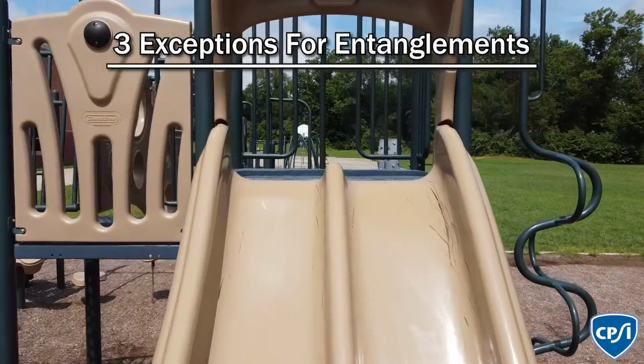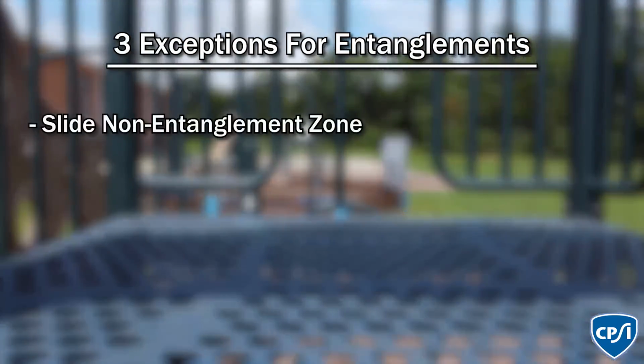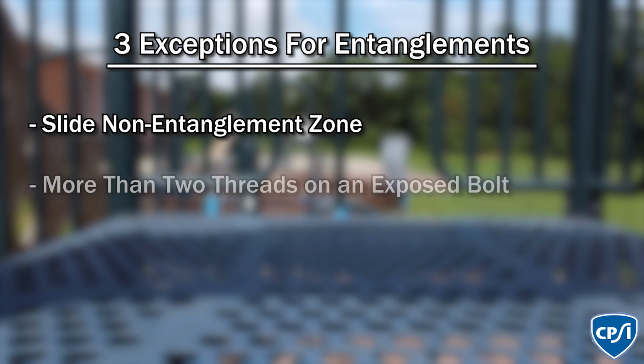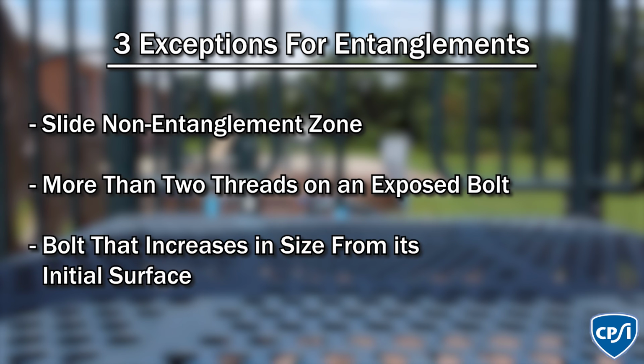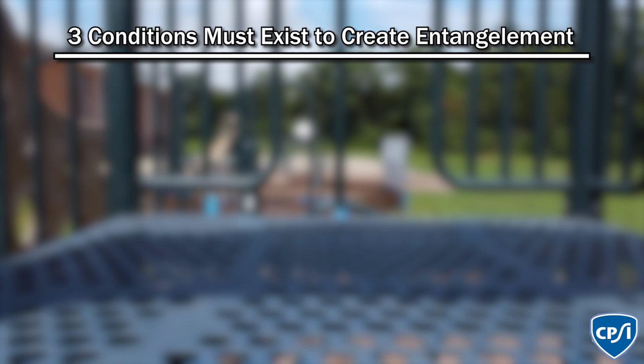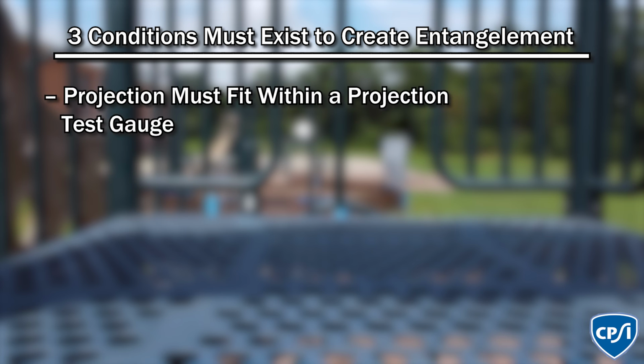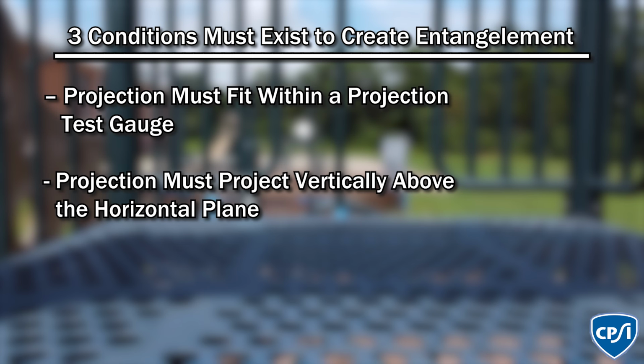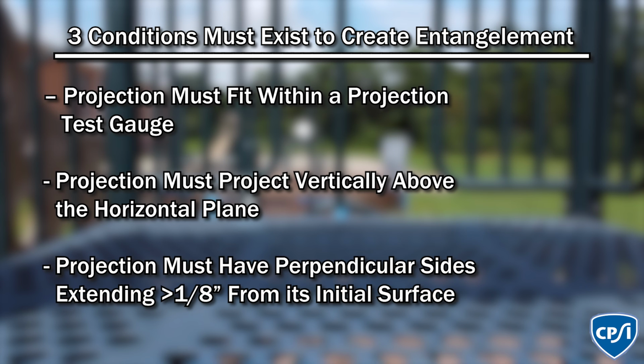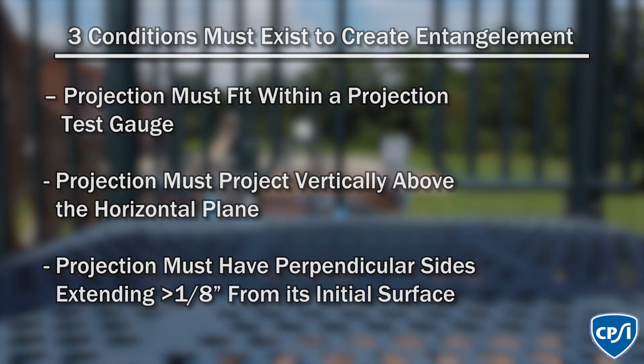Remember the 3 exception and condition rules. Slide non-entanglement zone, more than 2 threads on an exposed bolt, bolt that increases in size from its initial surface. The 3 conditions. Projection must fit within a projection test gauge. Projection must project vertically above the horizontal plane. Projection must have perpendicular sides, extending greater than 1/8 inch from its initial surface.